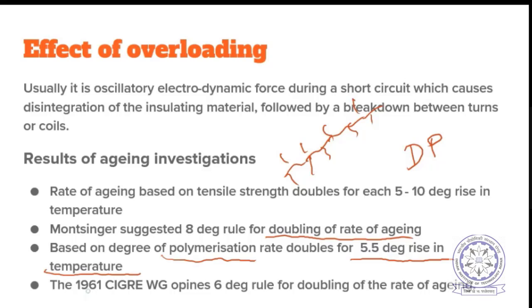But in 1961, the CIGRE working group opined that a 6-degree rule applies for doubling of the rate of aging. So normally the 6-degree rule is adopted. So for every 6 degrees centigrade rise in the temperature, the rate of aging is expected to double. So these are the results of aging investigations. Let us see next.